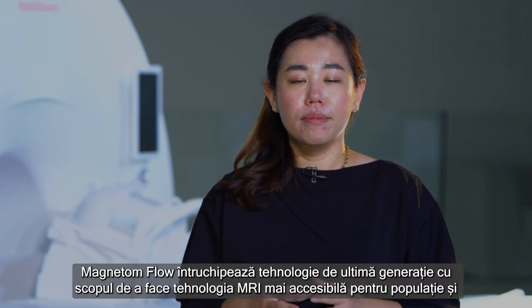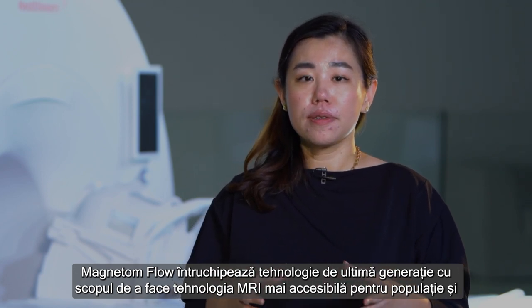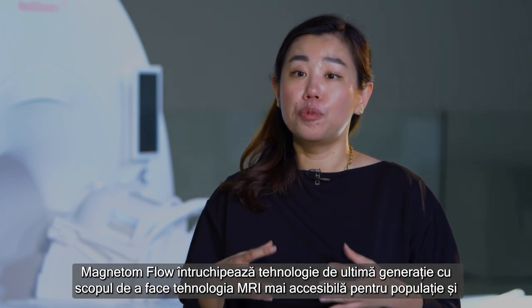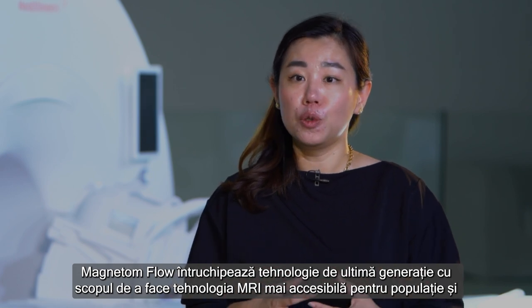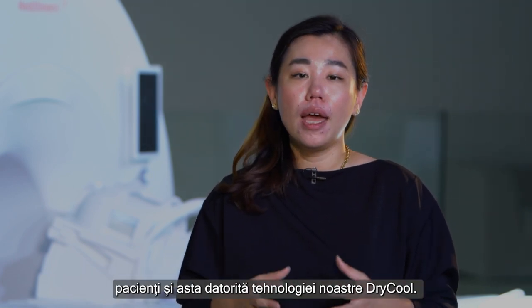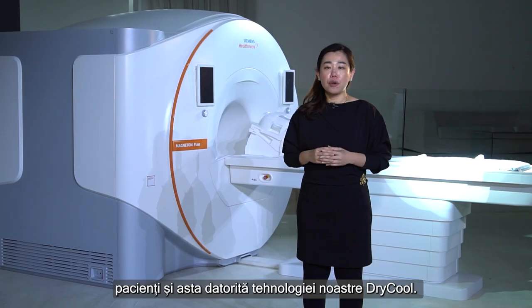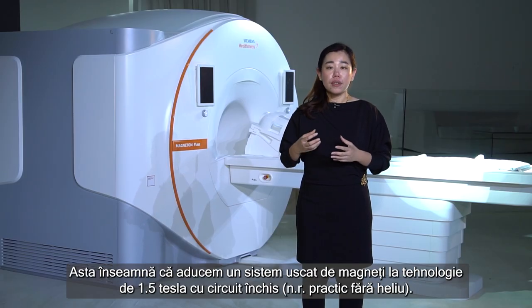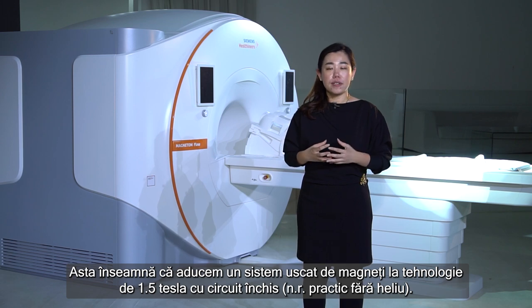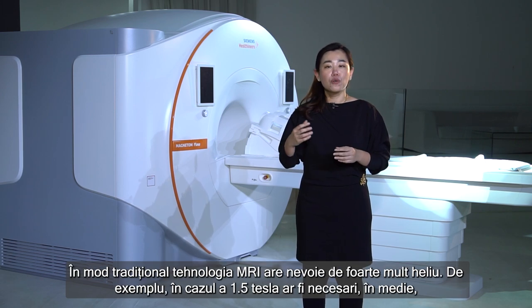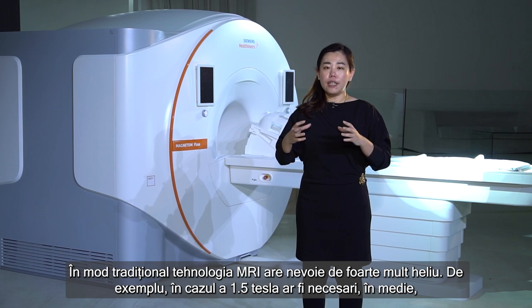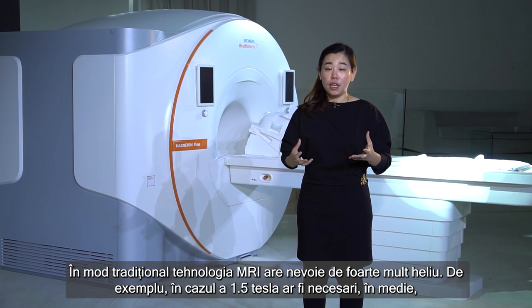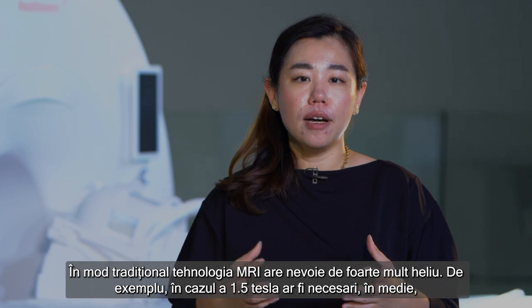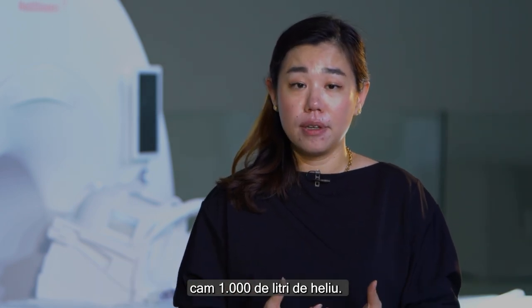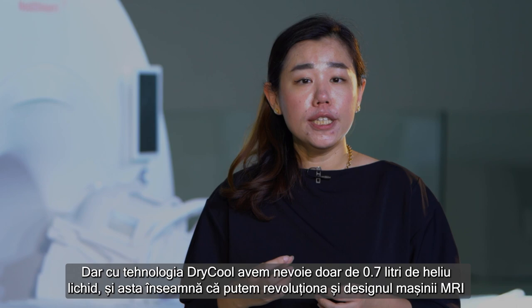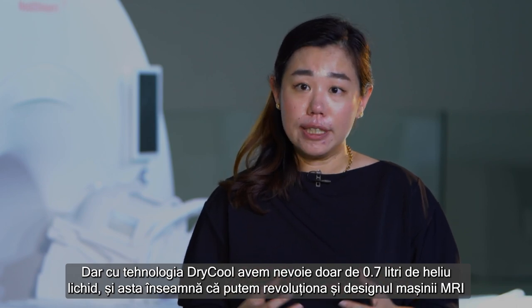So Magnetom Flow really embodies the latest technology in order to bring MRI to be more accessible to people, to patients. The foundation of this is based on our DryCool technology. This means we bring a dry magnet system at 1.5 Tesla. Traditionally, MRI needs a lot of helium - for example, for a 1.5 Tesla system, about an average of 1,000 liters. But with DryCool technology, we only need 0.7 liters of liquid helium.